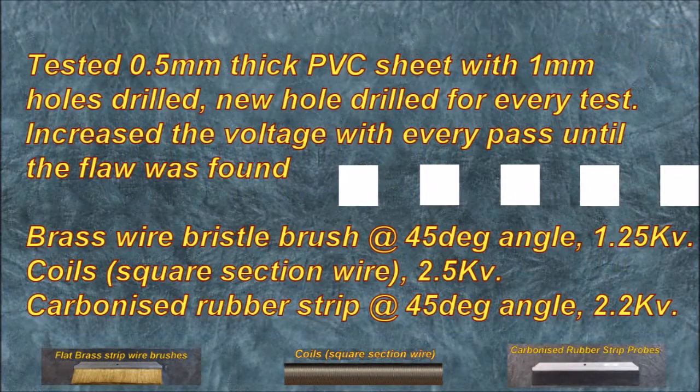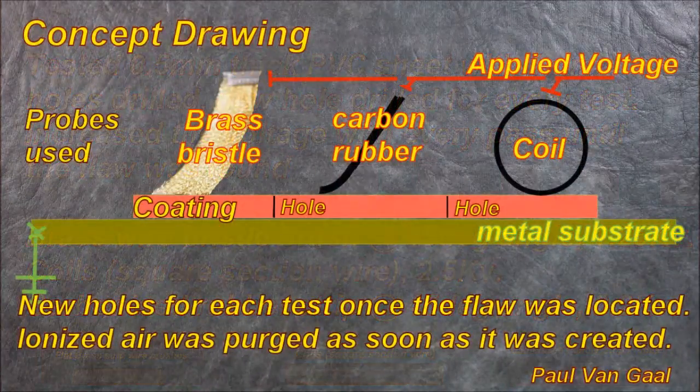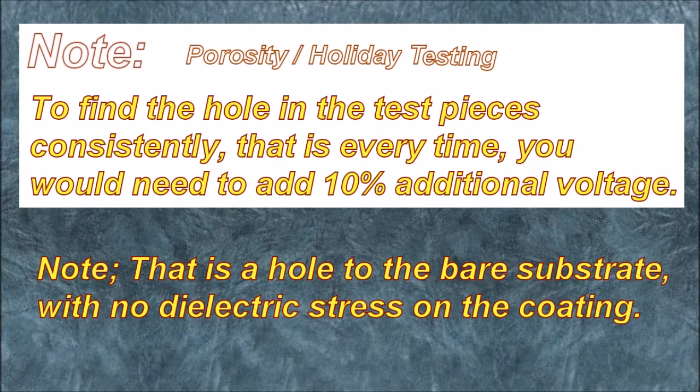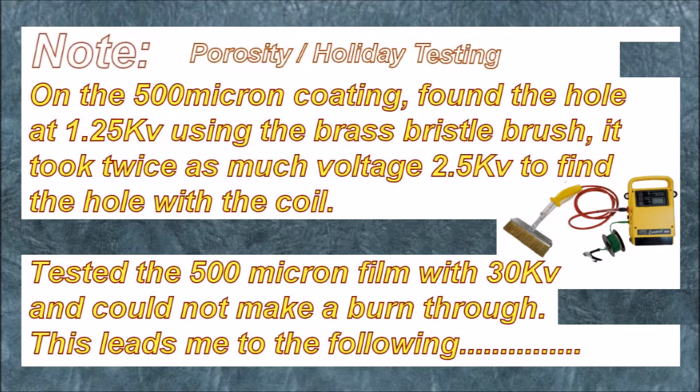Tested 0.5 mm thick PVC sheet with 1 mm holes drilled in it — new hole drilled for every test. Increased the voltage with every pass until the flaw was found. Brass wire bristle brush at 45° angle: 1.25 kV. Coiled square section wire: 2.5 kV. Carbonized rubber strip at 45° angle: 2.2 kV. To find the hole consistently, you would need to add 10% additional voltage. Note: that is a hole to the bare substrate with no dielectric stress on the coating. Do these tests indicate that you need to use a brass bristle brush on all irregularities, or just use brass brushware on all surfaces? Now you have seen why a brass bristle brush is the best probe to use — everything else is just a shortcut. On the 500 micron coating, found the hole at 1.25 kV using the brass bristle brush; it took twice as much voltage — 2.5 kV — to find the hole with a coil.